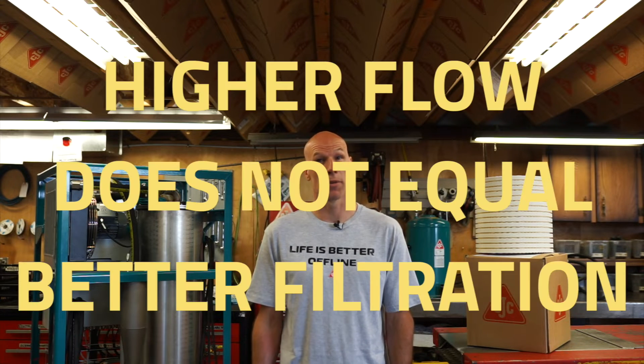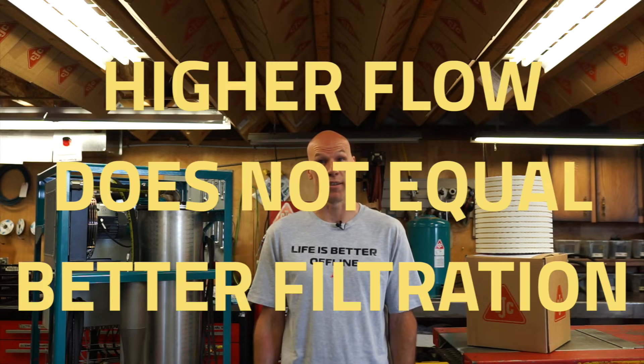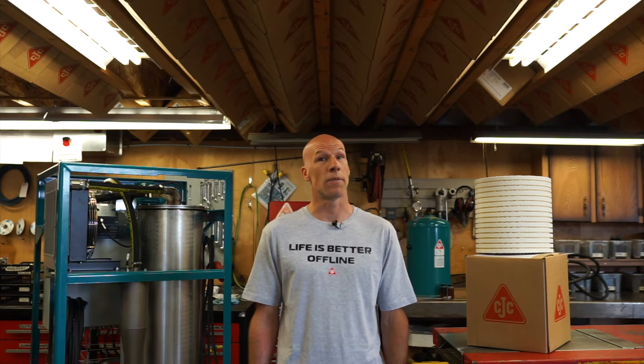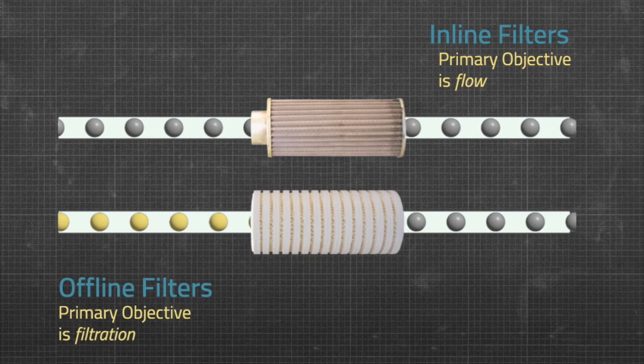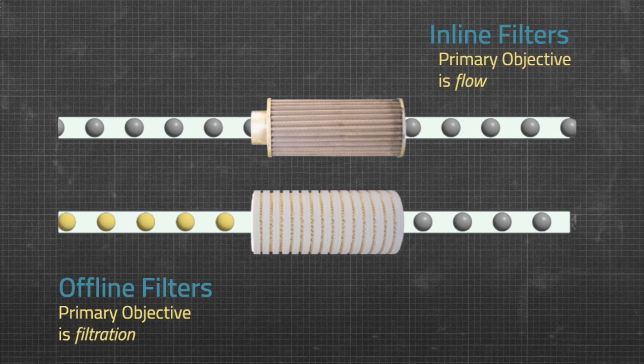Here I have to point out a common misconception: higher flow does not equal better filtration. You could make the argument that the faster you push a liter of oil through a filter, results in more liters being cleaned in a certain time. But the beauty of an offline filter is that by utilizing higher efficiency and finer filter media, you can do a much more thorough job of cleaning each liter of oil that passes through the filter.